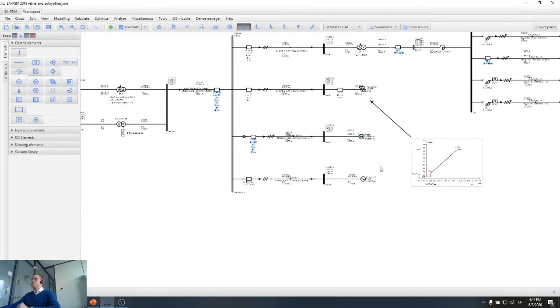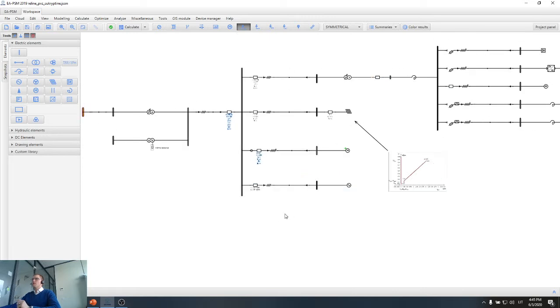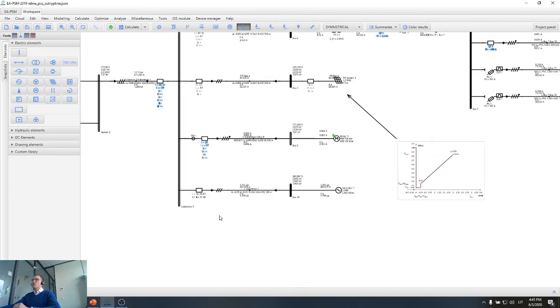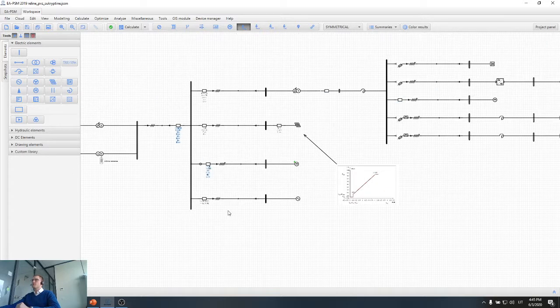So in software also the user can set directional protection devices. Earth fault directional protection devices can also be used. However, as I have mentioned, this is a very broad topic, so we cover all these things during EA-PSM Academy. What is more, we also have distance protection, which allows to work with high voltage networks protection coordination.